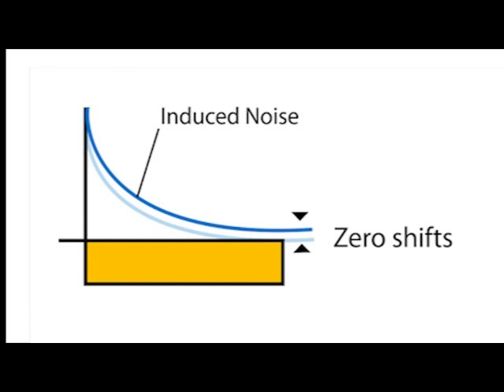This results in zero point shift or fluctuation. Process or ambient temperature changes result in property changes in a process liquid, such as conductivity or permittivity, which varies the magnitude of eddy currents that come into the electrode. Therefore, process ambient temperature change can cause zero shift or fluctuation.